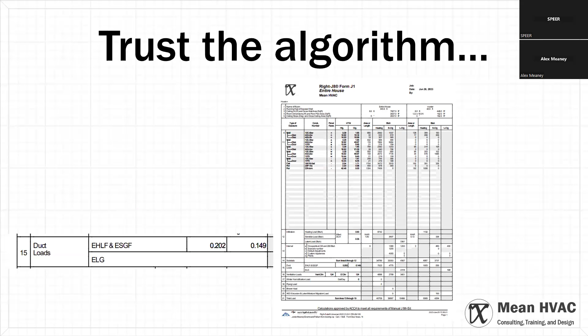Because we use AHRI, right? Step one—there's a Spear tutorial I gave on this called 'There's No Such Thing as a Ton.' Because there isn't: a ton is a unit of weight, and in the HVAC world a ton is not a certain number of BTUs. Actually, it is—it's 288,000. Let that sink in for a second. We're not going to tear that apart, it'll take all day, but the idea that 12,000 BTUs per ton is a real thing—it's not, even looking at AHRI data to tell me that.